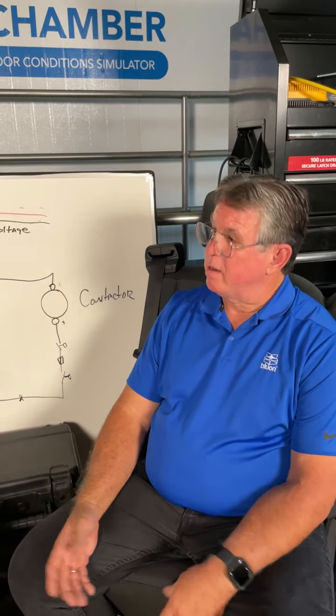Now I can jump from R to Y and see if it comes on. If it comes on, great. Taking the thermostat off the wall, leaving the subbase. Yep. Jumper from R to Y at the subbase. See if the condensing unit comes on. Yep. We say that like it was a no-brainer, but it's not.